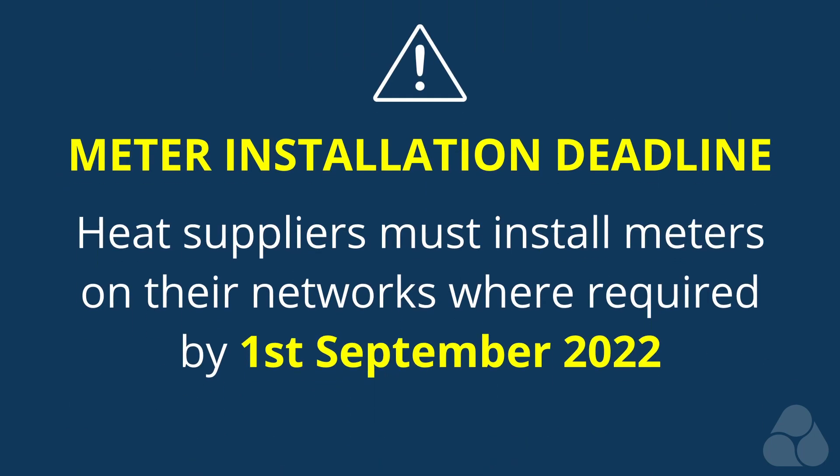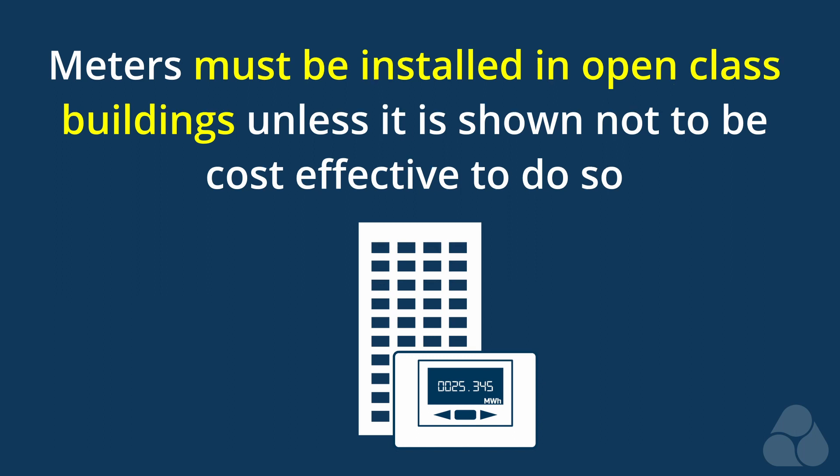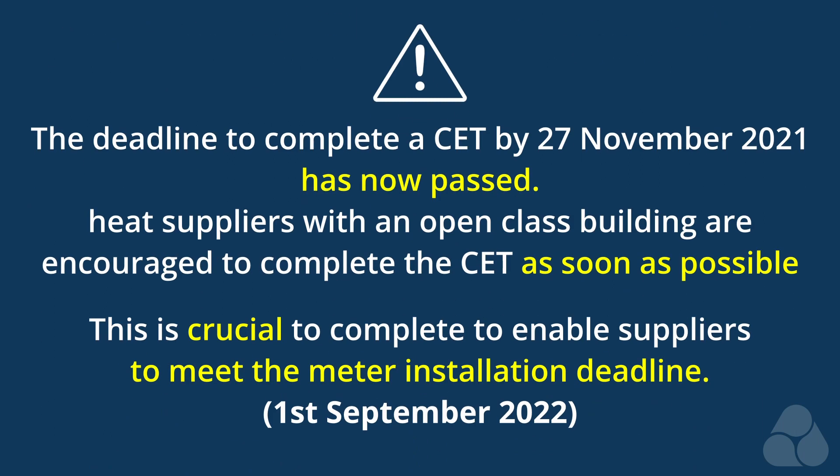Heat suppliers are required to install meters on their networks where required by the 1st of September 2022. If a building is in the open class, a meter must be installed unless it is shown not to be cost-effective to do so. The deadline to complete a CET by the 27th of November 2021 has now passed. As such, heat suppliers with an open-class building that have not yet done so are encouraged to complete the CET as soon as possible to enable them to meet the meter installation deadline.